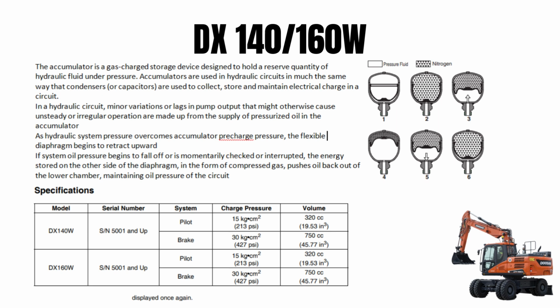So at first position, no nitrogen inside this accumulator. This is pressure fluid. Some accumulators are filled with pressure fluid and some with gas nitrogen. In the second photo you can see this filled with nitrogen, no pressure at point 2 of the accumulator. When hydraulic pressure comes, at number 3 position, you can see this will push the diaphragm of the accumulator upside. This will store the energy. At number 4 you can see the position of the diaphragm. Number 5, now this is releasing the stored energy in the form of hydraulic stored inside. So number 6, all the hydraulic released.